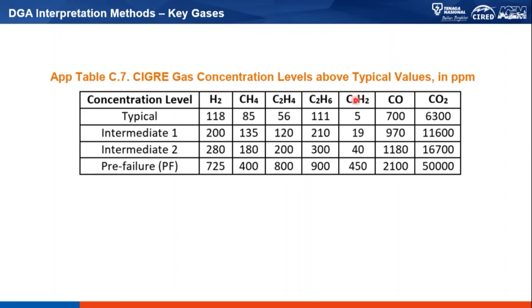Right, so next we are going into the ratio method. The ratio method is another method for interpreting the incipient fault within the transformer. This is what we call the IEC 60599 method.